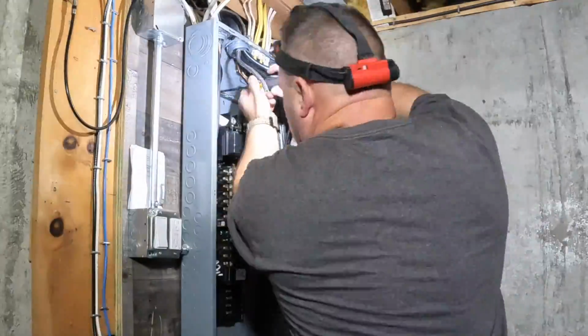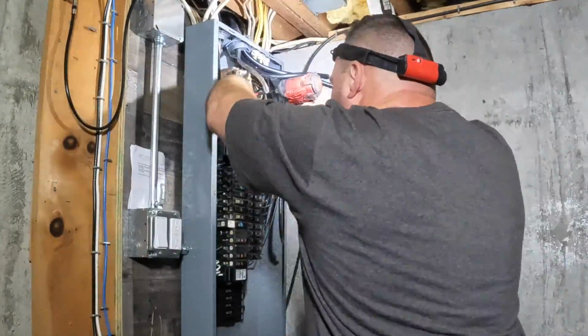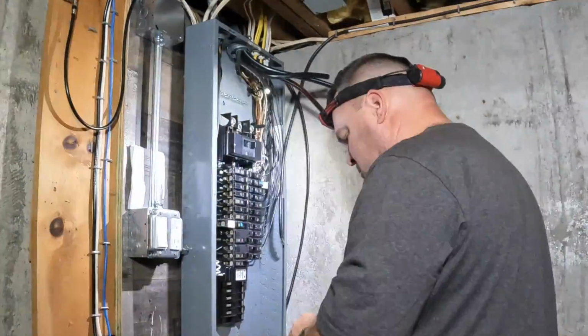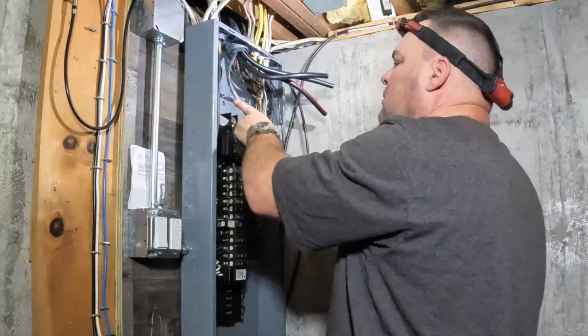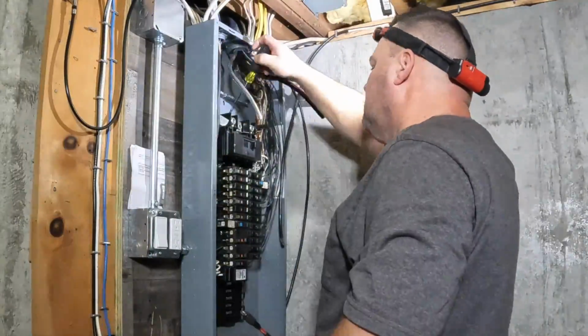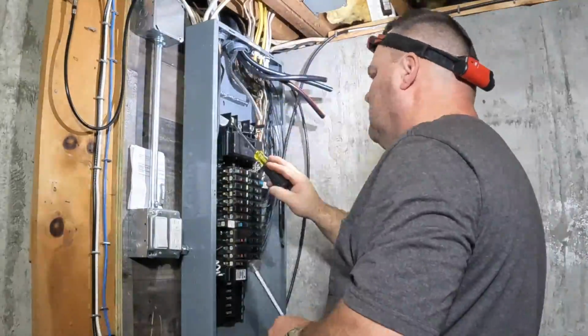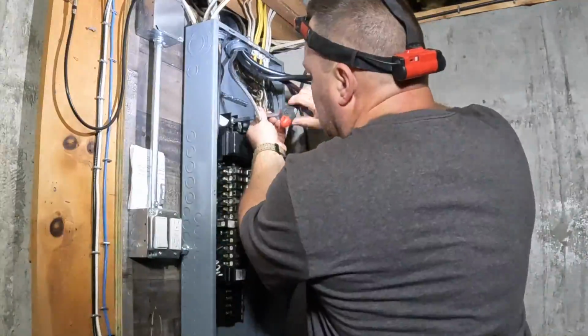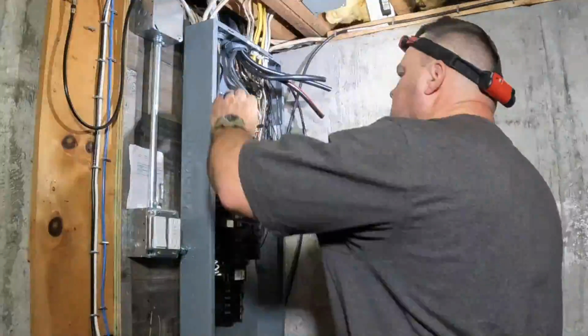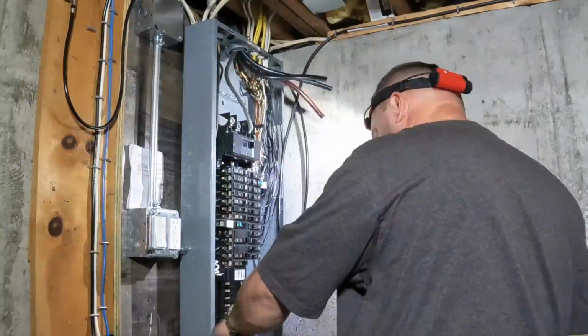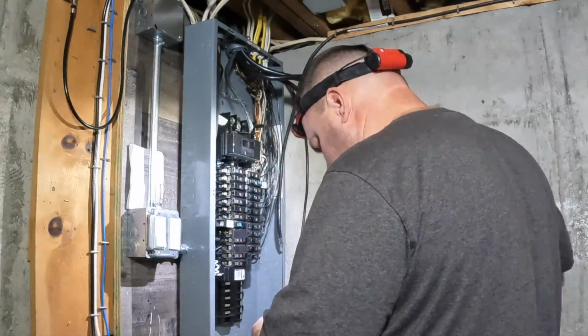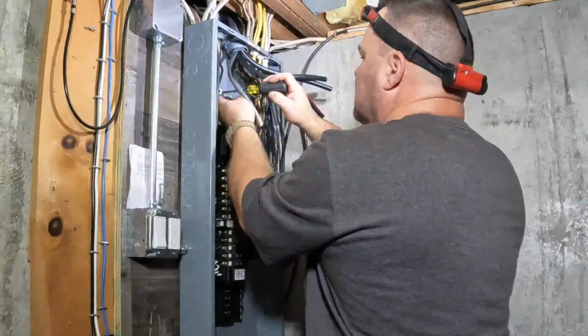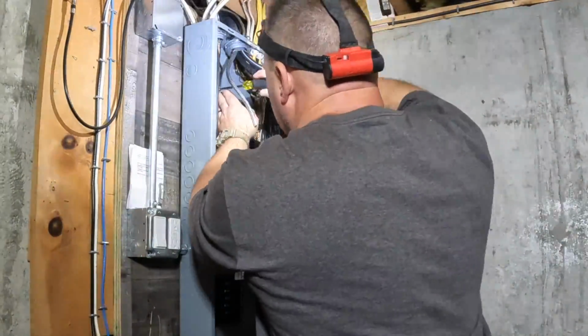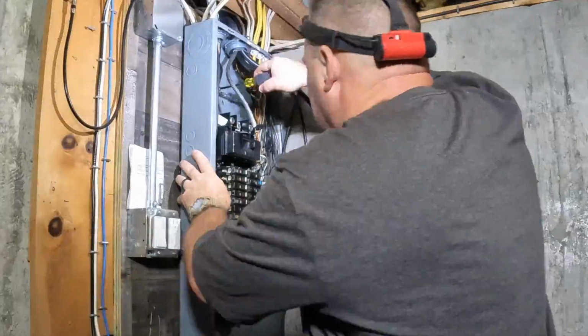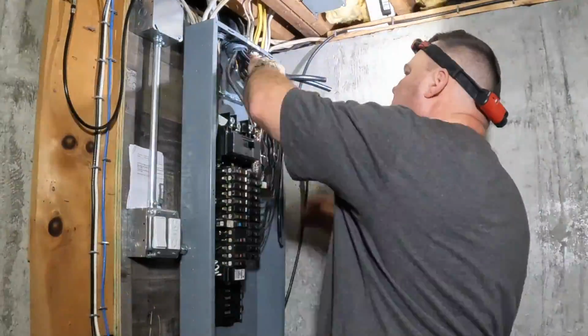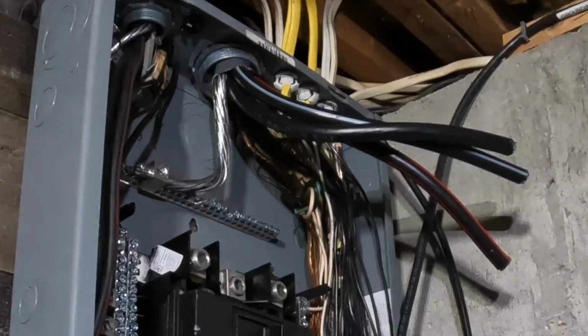So you need to drill a couple of pilot holes, and I'm just using a hand threader right here to thread the enclosure so that I can use the required bolts that come with the equipment grounding bus, specific just for the Square D panel here. And then we're also going to add a lug large enough for 2-aught aluminum, which is what the equipment grounding conductor is in a 4-wire service entrance riser cable for a 200 amp main lug only panel, which is what this will be once we're done wiring.